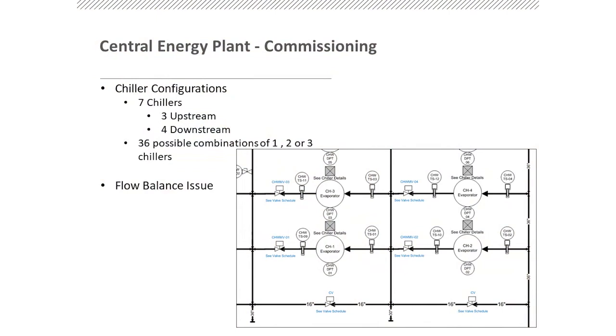And so let's now talk about some of the issues of testing out this chiller plant. In the flow diagram, you can see the different chillers and the lineups. I've already told you that any upstream chiller can work with any downstream chiller. So when you tell your client, we're going to test for every mode, well, what does every mode mean? Does that mean upstream and then downstream, or downstream then upstream? In reality, Jonathan sat down and did all the iterations, and you see the number up there: there are 36 different possible configurations of staging of chillers because they can all work with each other.